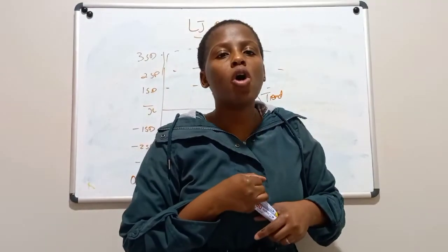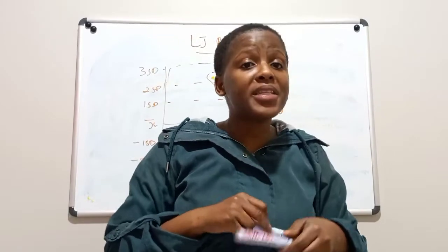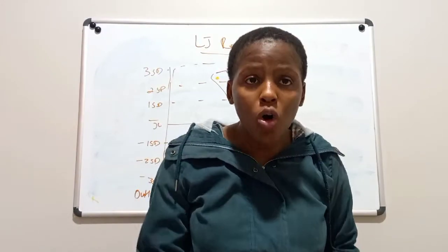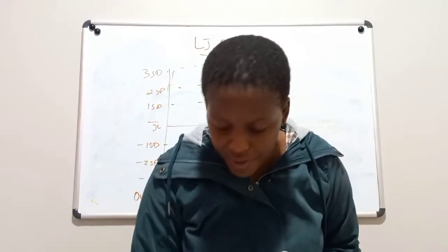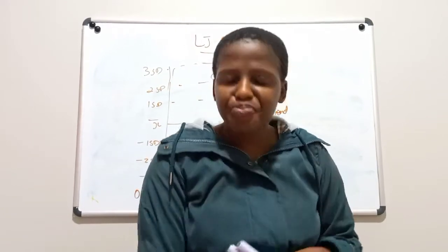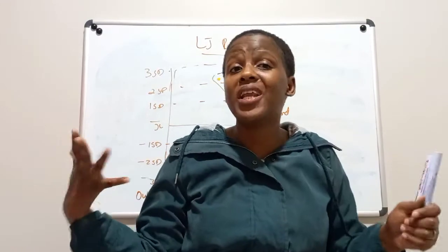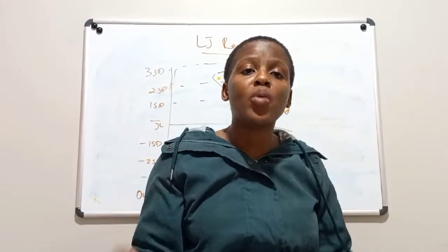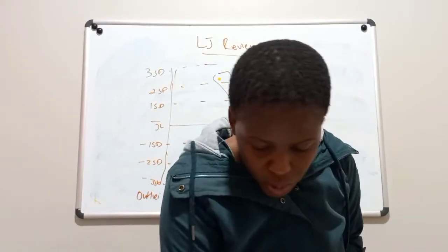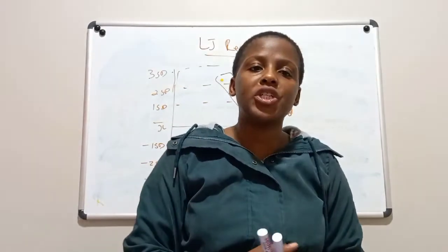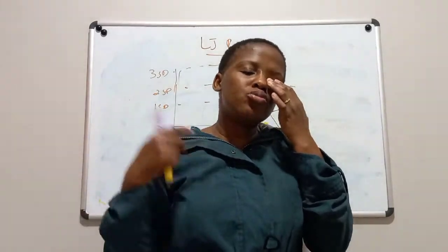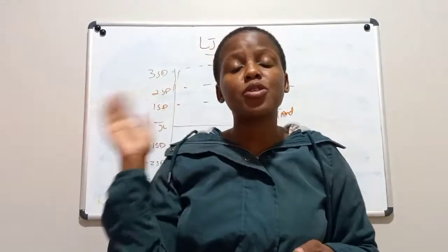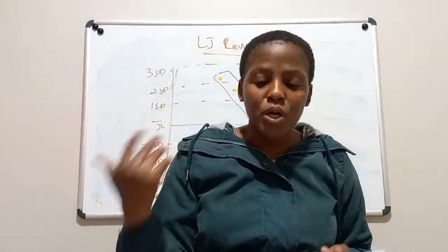A trend can be caused by the stability of the reagent. If your reagent has been in your machine for quite some time and it's getting old, then you will see a decrease of the values. Or it can also be due to your halogen lamp needing replacement, maybe it's been there for some time. Or the QC material that you're using, we will question its stability, and we'll also question your calibration status. Maybe you haven't calibrated this analyte recently, and now your QC sample starts to either go down or go up. So basically that is the trend.